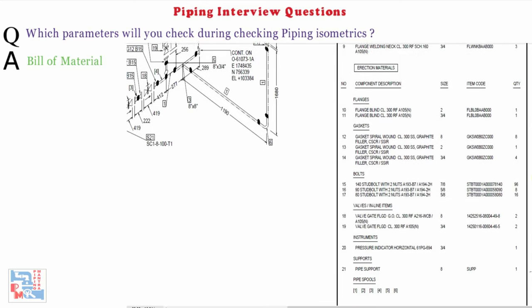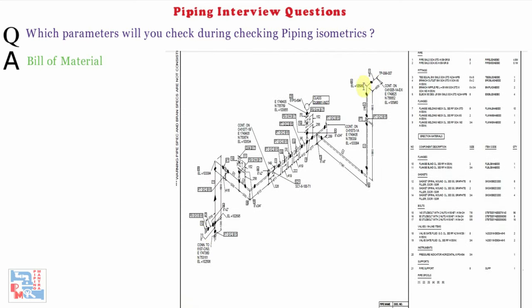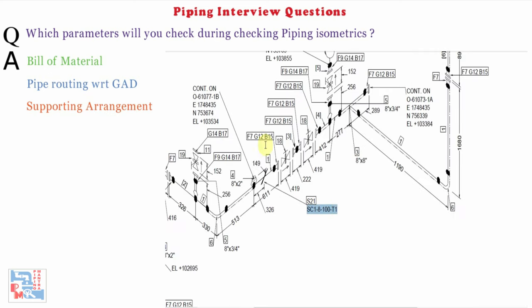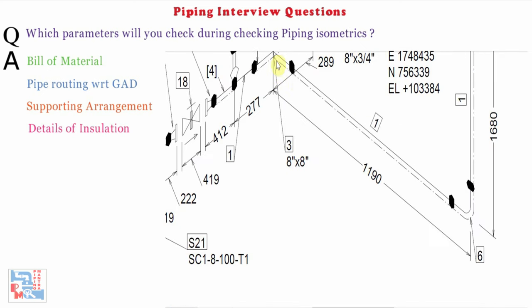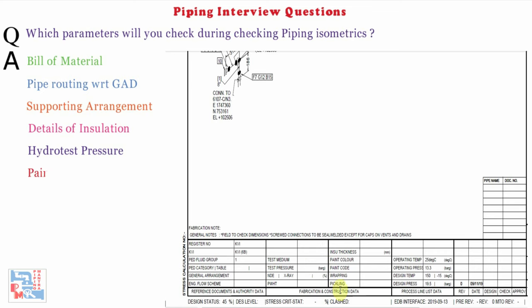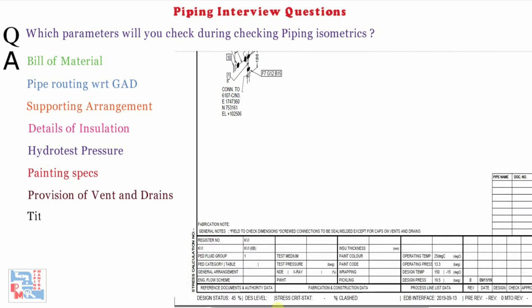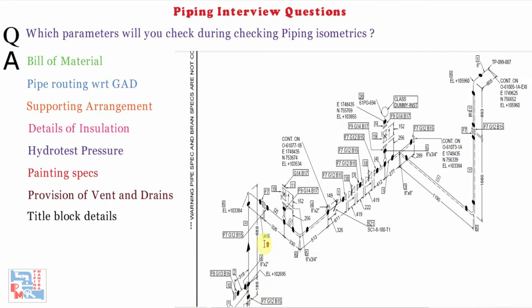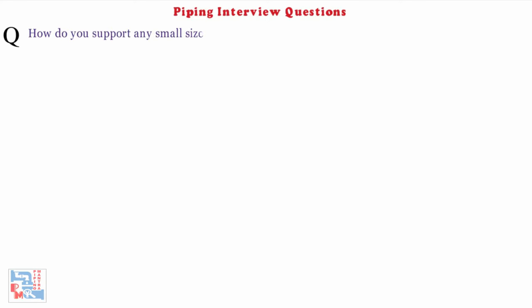First question: which parameters will you check while checking piping isometrics? Bill of material, pipe routing with respect to general arrangement drawing, supporting arrangement, details of insulation, hydro test pressure, painting specs, and provision of vents and drains at appropriate locations.